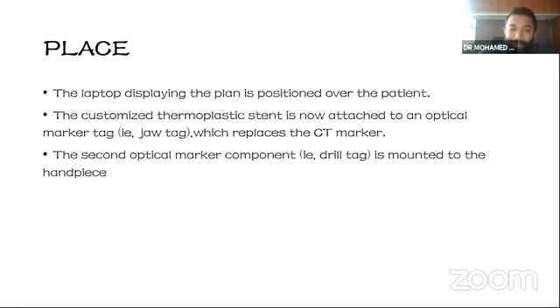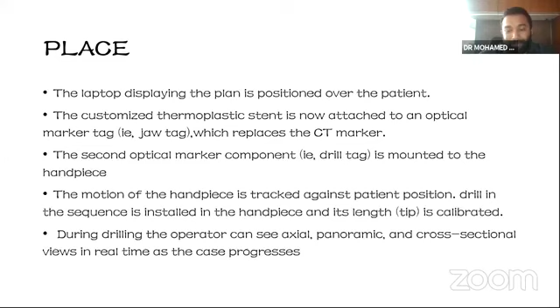The drill in the sequence is installed in the handpiece and its tip is calibrated. For each drill we have to calibrate. Then only can we ensure the drill is going to our planned site. During drilling, the operator can see axial, panoramic, and cross-sectional views in real time as the case progresses. This is the main advantage. We won't go wrong in this system. We will be aware that what we planned will be exactly executed.